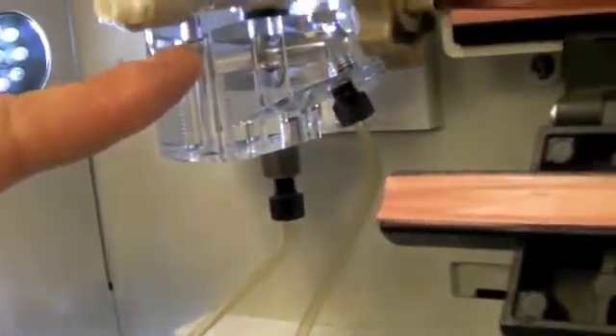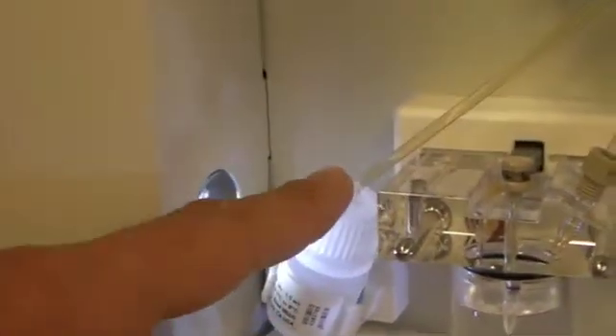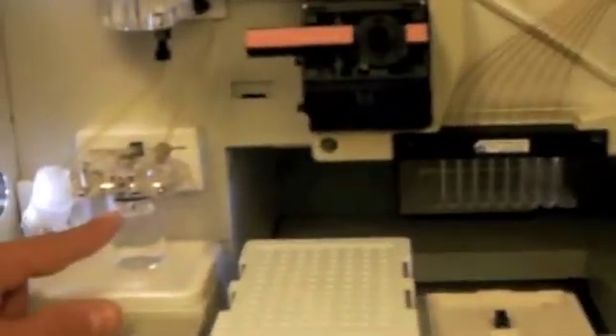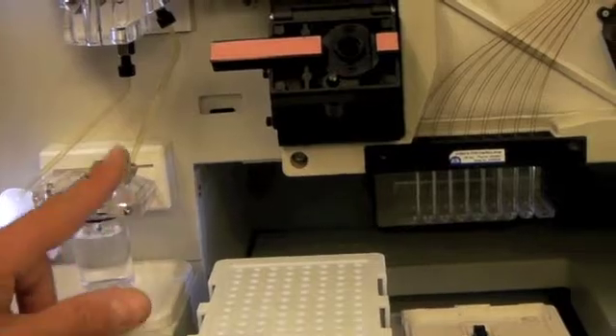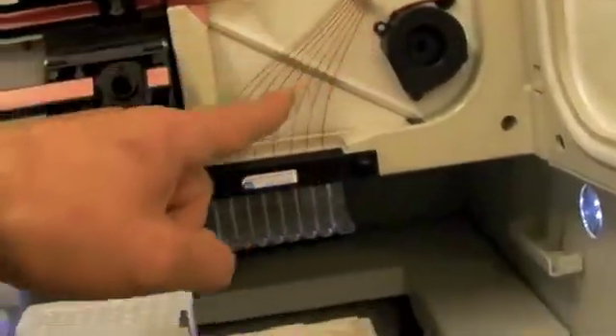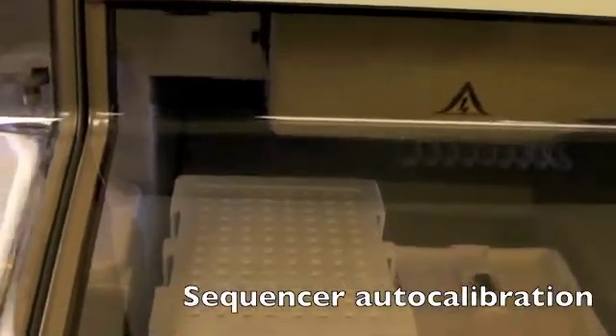Now the rest of the assembly is a polymer pump which fills up the capillaries with polymer. Here's our polymer source right there, $150 a bottle. And of course we have a buffer chamber which completes the electrophoretic circuit. There's another electrode in there, and you can see the circuit right there. The second electrode is the needles themselves.